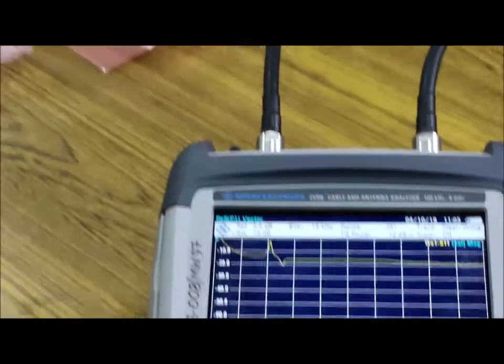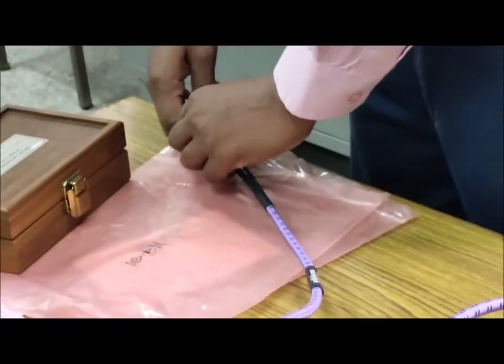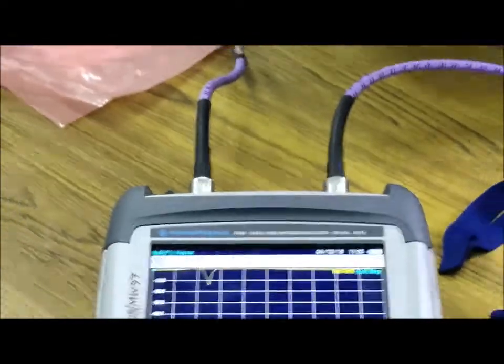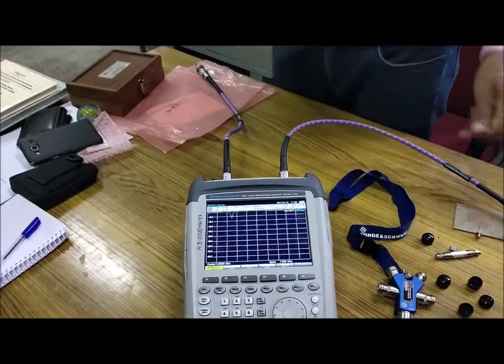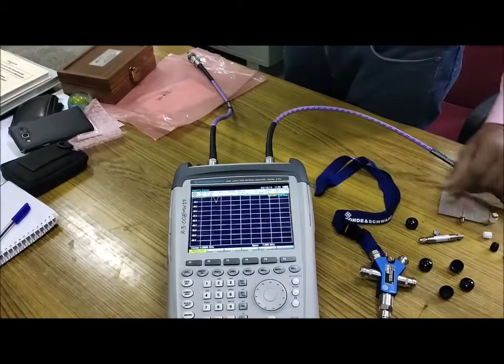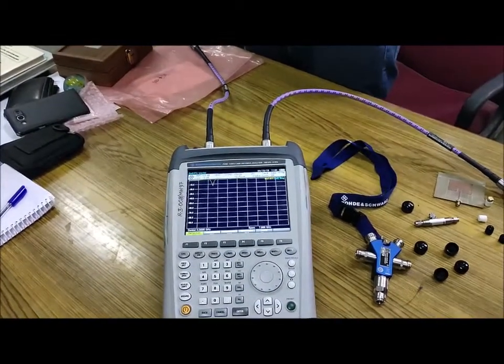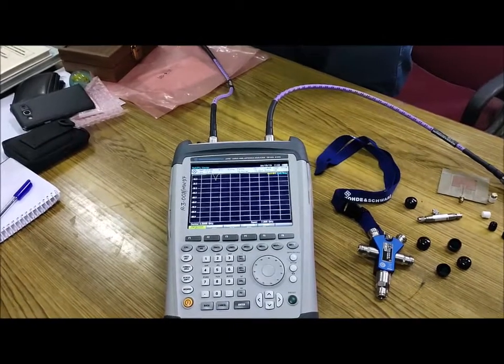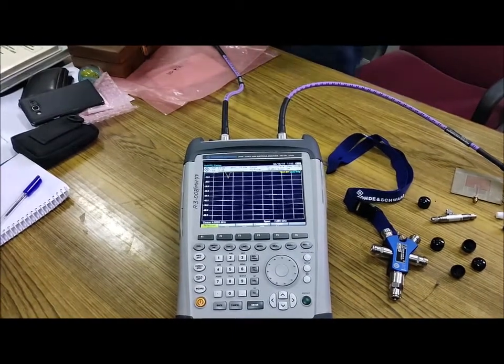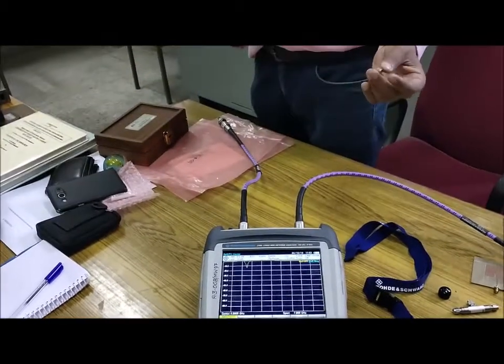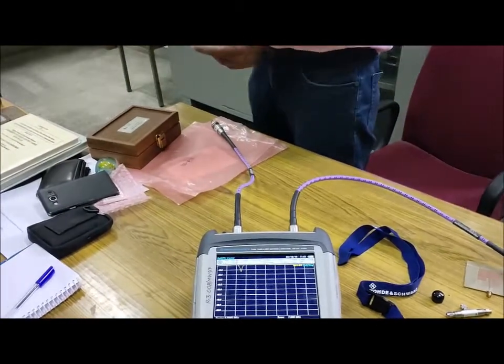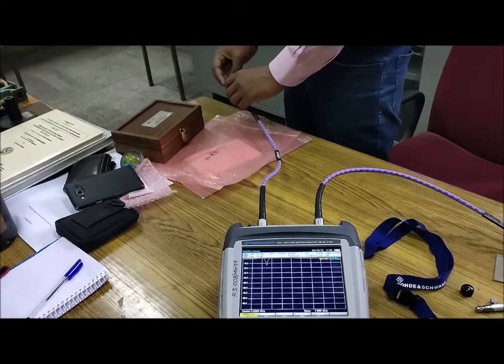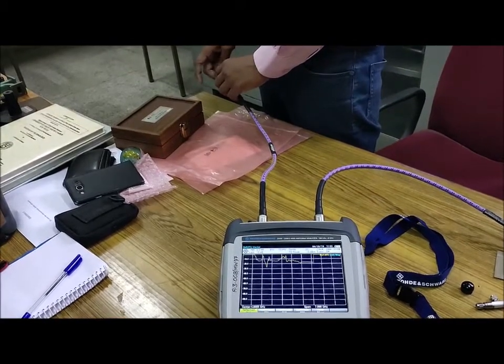And let me check any other arbitrary number, any other device. So after the calibration, I need to connect to the DUT. I verified that the value of return loss for the matched load is from 20 dB to 40 dB, which is a suitable range for the matched load. So now I am using a DUT, an unknown load. Although I know this is a matched load, let's assume this is an unknown load.